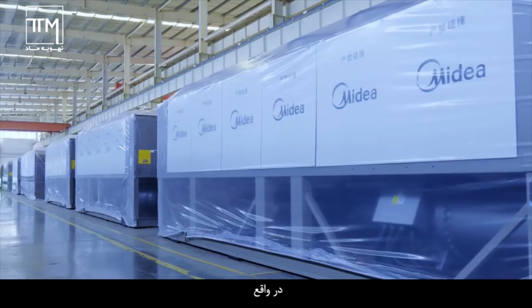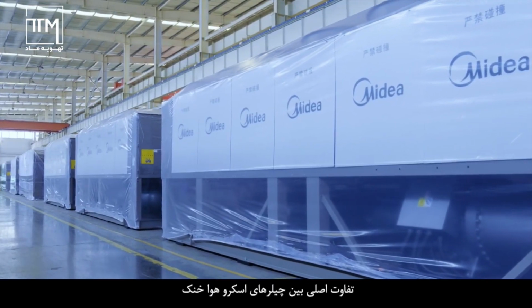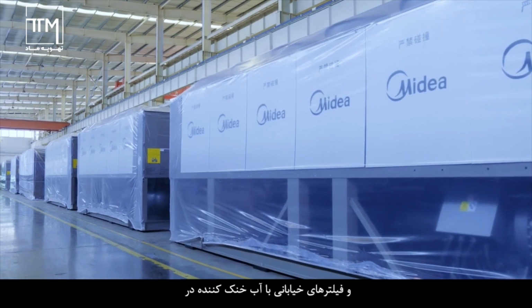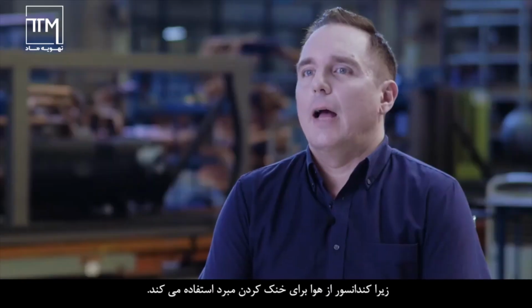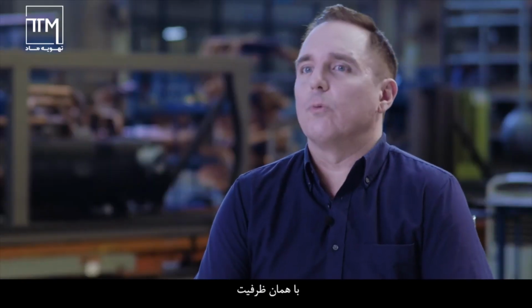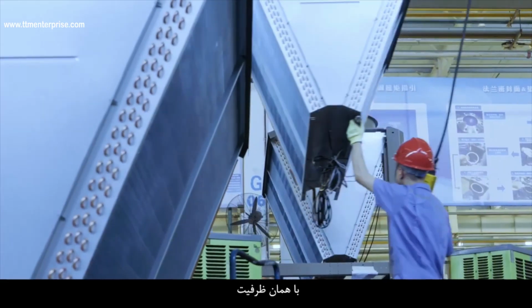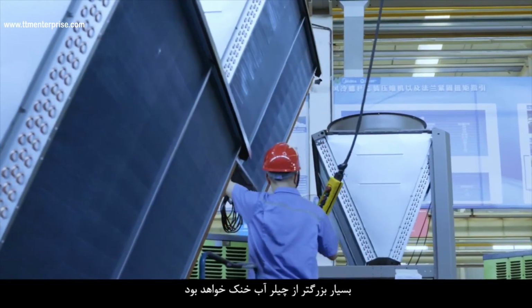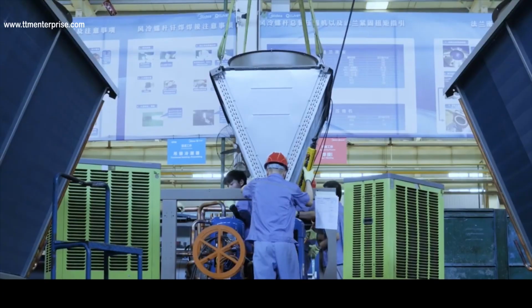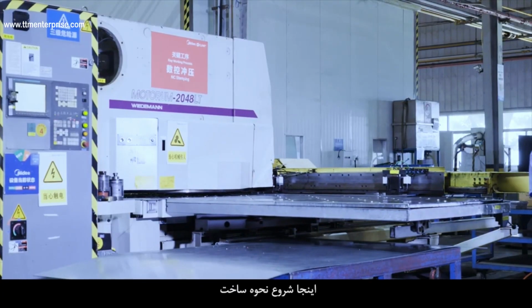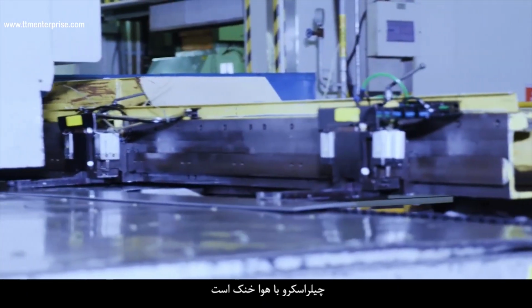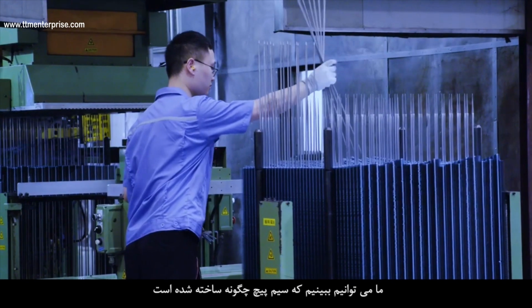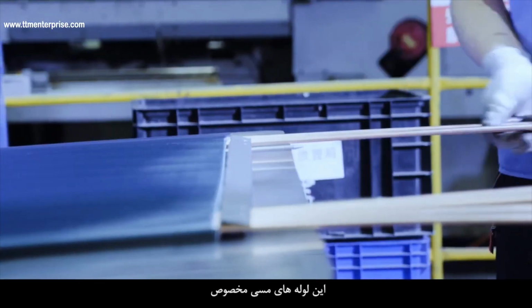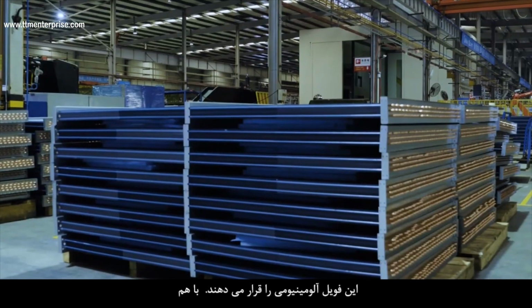In fact, the main difference between air-cooled screw chillers and water-cooled screw chillers is the condenser. As the condenser uses the air to cool the refrigerant, at the same capacity, the size of the air-cooled chiller will be much bigger than the water-cooled chiller. Here's the start of how we make the air-cooled screw chiller. We can see how the coil is made. These special copper pipes will put these aluminum foil together.